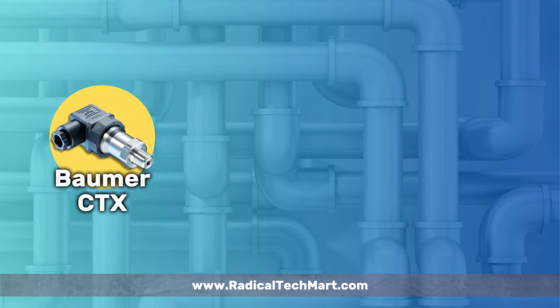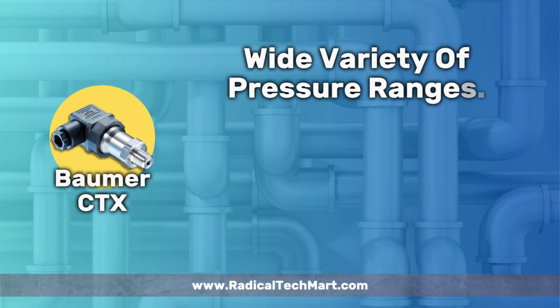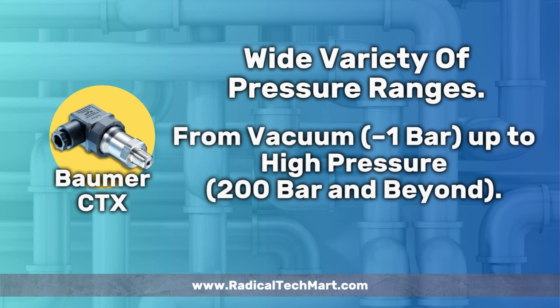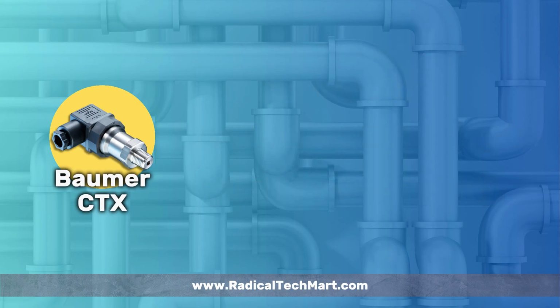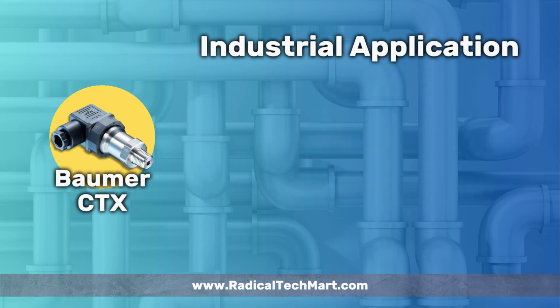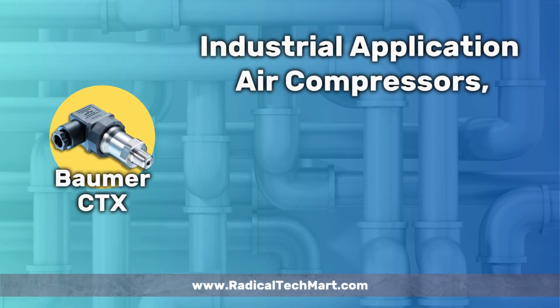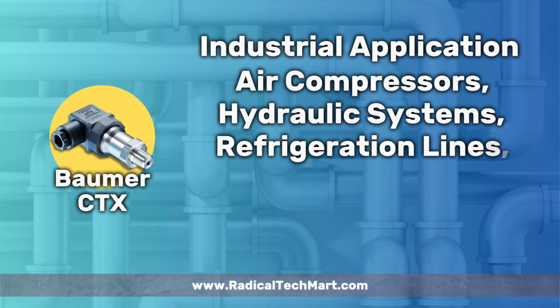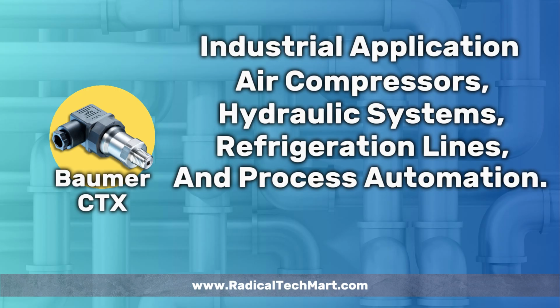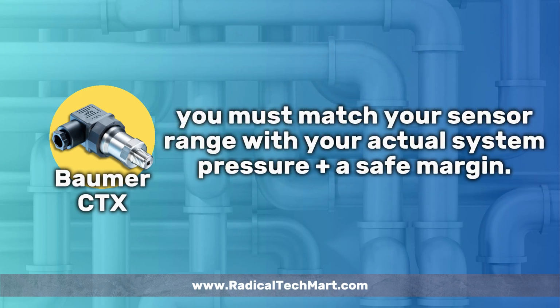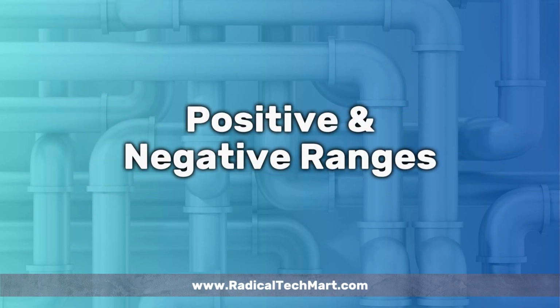First, the Baumer CTX series is available in a wide variety of pressure ranges, from vacuum, -1 bar, up to high pressure, 200 bar and beyond. These ranges cover almost every industrial application: air compressors, hydraulic systems, refrigeration lines, and process automation. But to get the best performance, you must match your sensor range with your actual system pressure plus a safe margin. Now, let's talk about positive and negative ranges.